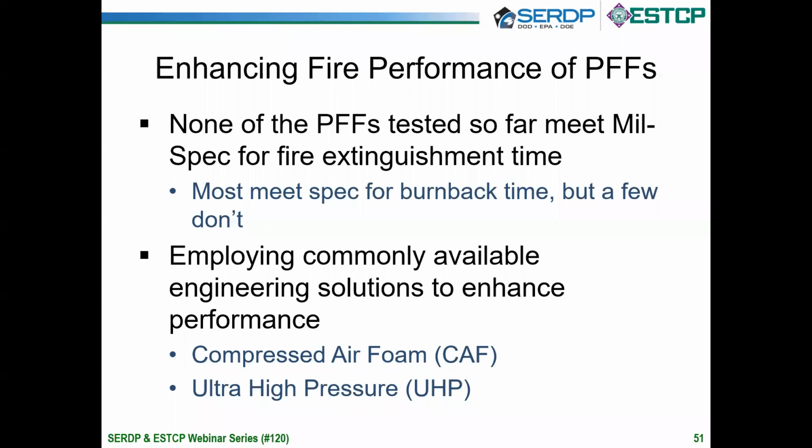So we confirmed in this project very early that none of the products we tested meet the mil spec for fire extinguishment time. And we also found that while most meet the spec for burn back time, a few don't meet that spec either. So how do we improve the performance of these products?